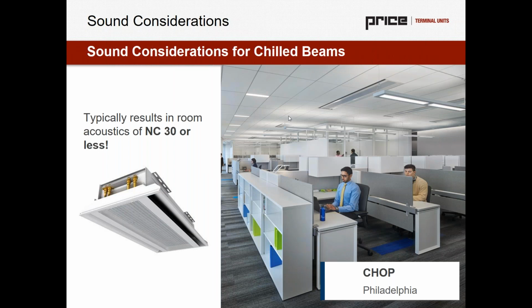So the other portion of this holy matrimony, flying back to chilled beams here, I think chilled beams, especially in a hybrid kind of solution, can really provide some significant value acoustically. Typically, we're seeing room acoustics of NC30 or less in chilled beam type applications. And I show this one example of an office in Philadelphia in particular, because in this project, you can see the active chilled beams in the system. This is a Price chilled beam project that actually ended up being too quiet for the office.